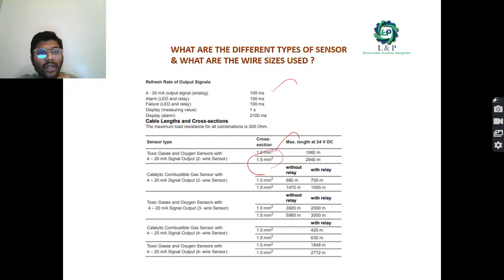If you're going to measure any sort of catalytic combustible gases, for example with 3-wire sensors, for a 1 square mm cable, without relay you can use up to 980 meters. With the relay, you can use up to 700 meters. And for a 1.5 square mm cable, without relay it is 1470 meters. With relay, it's 1050 meters. So this is basically how you go with a 3-wire connection.